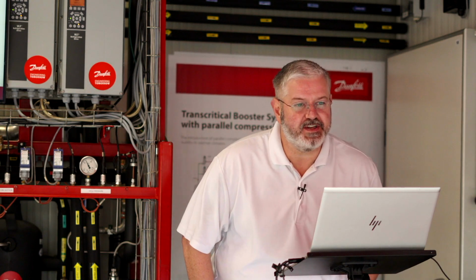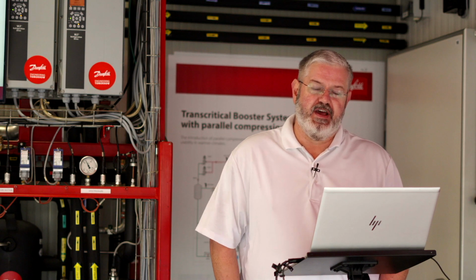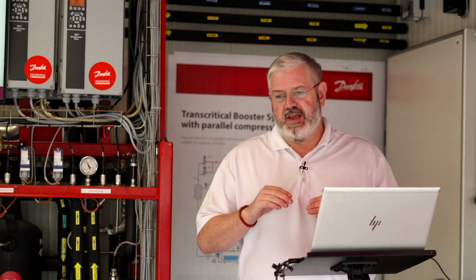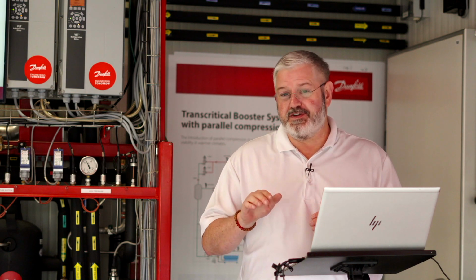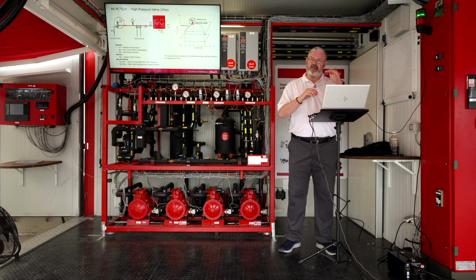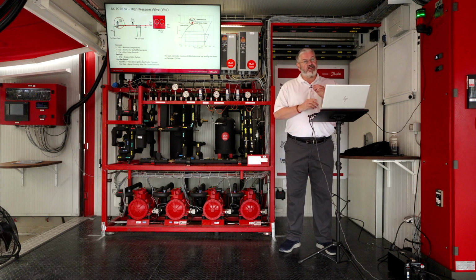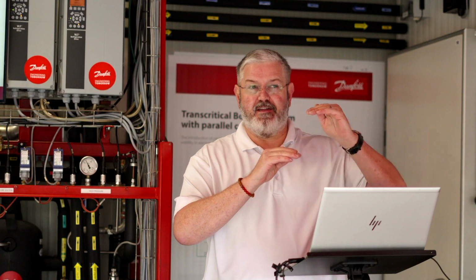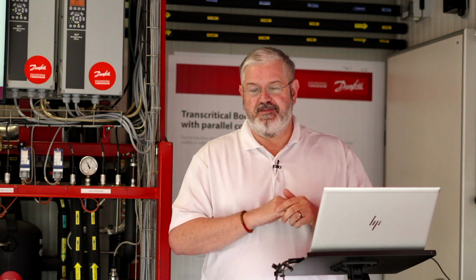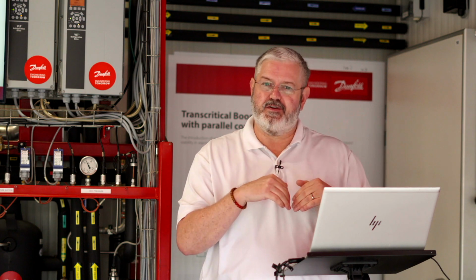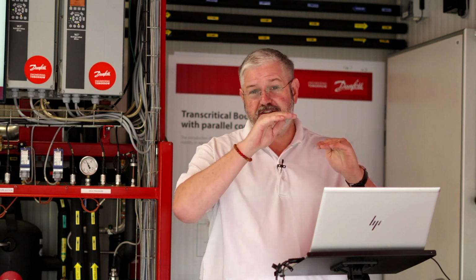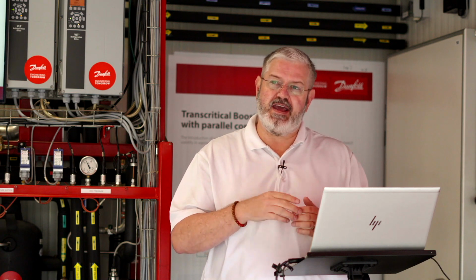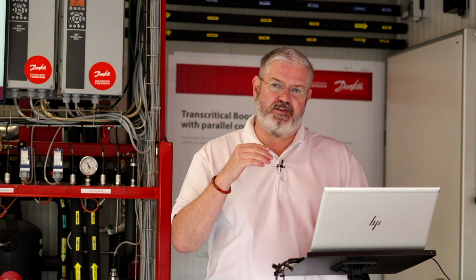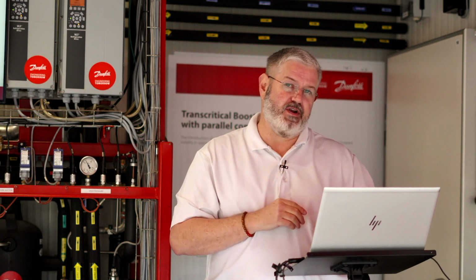So we have a question that says, do you always want the gas cooler operating in the transcritical zone? The answer to that is really no. Operating in the transcritical zone is based on ambient temperature. If you picture inside the gas cooler, I've thrown out the number of 87 degrees several times because that's the actual critical point, but that's not really ambient. 82 degrees ambient would be your critical point if the outlet of the gas cooler is 5 degrees higher. So at 82 degrees ambient, you're really 87 inside the gas cooler. If the ambient gets below that, then you're below the critical point and operating in subcritical. So it transitions between the two throughout the year. Even on a summer day when you're 96 degrees at lunchtime and 72 degrees at night, you're transcritical at lunchtime and subcritical that night.